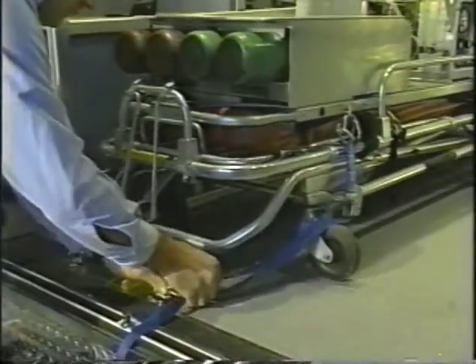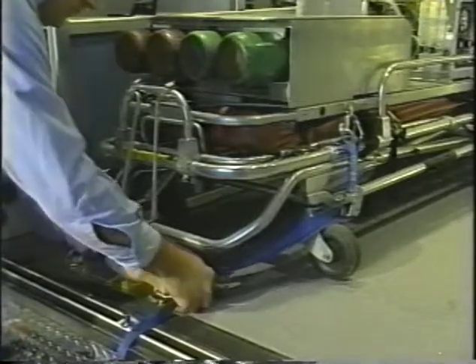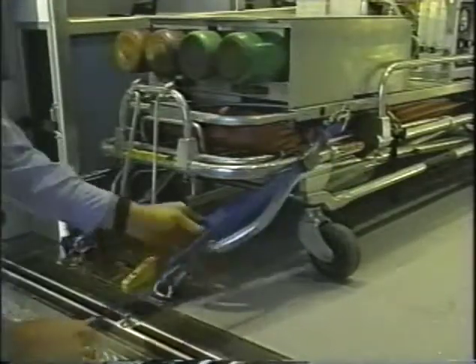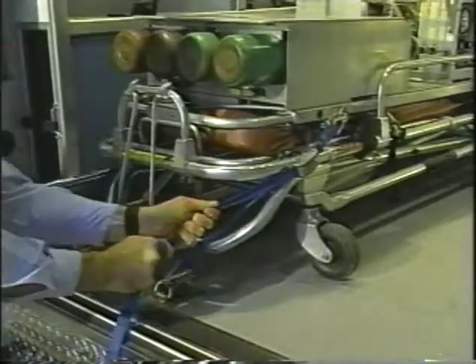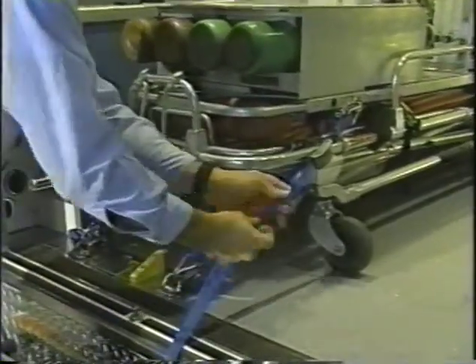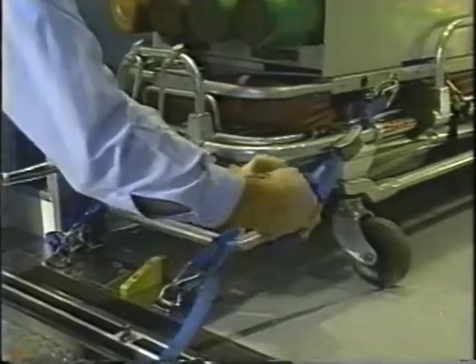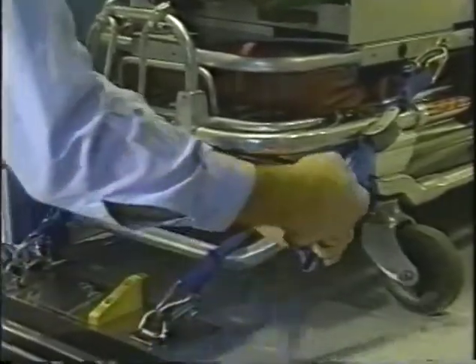Attach the end of the second strap to the rearmost D-ring on the right side of the incubator deck. Attach the other end to the right side floor-mounted tie-down bracket or floor ring. It is helpful to place the restraint straps to allow paramedics to pull the slack end towards them. Pull both strap ends tight for maximum effectiveness.